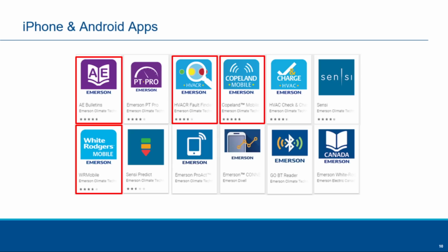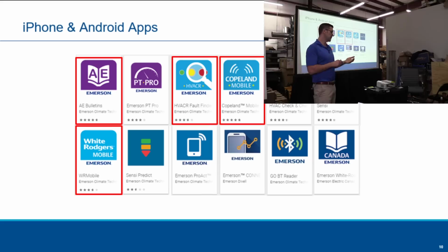HVAC Fault Finder. This is our CoreSense app. If you have any CoreSense in your Copeland compressors, you can use this app. But it's a diagnostics tool. So you can go in on the app, you're at your system and your system is not running. So you go on the app and you say, I do not have a compressor protector module. So you click on it, it says, does the compressor start? You click no. Does the compressor have voltage? Yes. Replace the compressor, or so on.